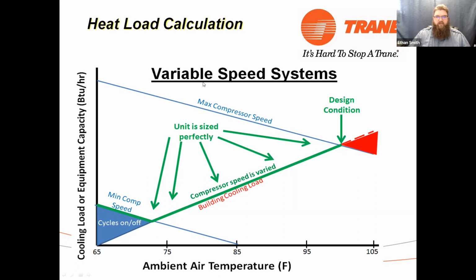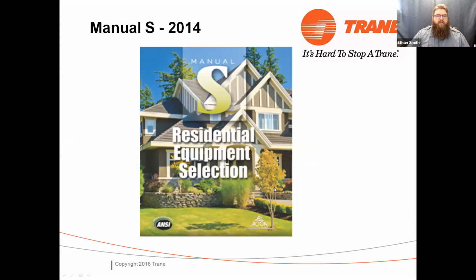You know, variable speed outdoor units for air conditioning have really brought zoning into what it wanted to be for the last 50 years. Everything else we've been kind of getting by, making do with what we had. But I'm a strong believer that the variable speed outdoor equipment has really brought zoning into what it should be. And so that's just kind of an example of different kinds of equipment we can do. We'll talk a little bit more about that in a little bit. But being able to match our design condition both for our total home and our individual zones becomes very important when we start talking about equipment selection, okay, which is next.